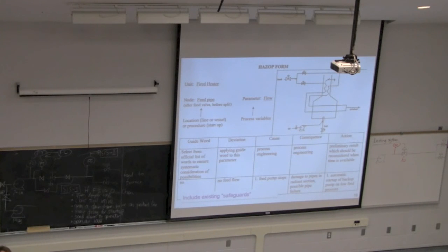Okay. So essentially, SIS is something we don't want to have happen to us. This is not something that happens on a daily basis, not even a monthly basis. SIS is for extreme situations. So going to these extreme levels where you're shutting the furnace fully, opening that damper 100%, blowing it out with air, just clearing out the situation to make it as safe as possible for the equipment and for the people around you. So we've spent almost 45 minutes just on one node, on one parameter. Okay.